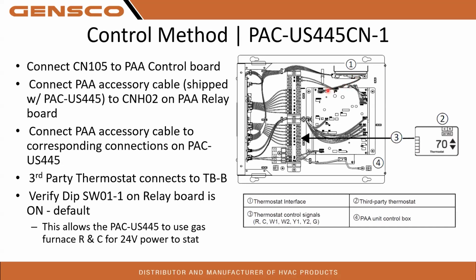The 445 does still have the CN105 connection, so you need to make sure that that's plugged in and wire up that pigtail. You should be good to go there. And also, again, on the relay board, SW01 number 1, even though it's supposed to be default from the factory on, verify that it is indeed on.